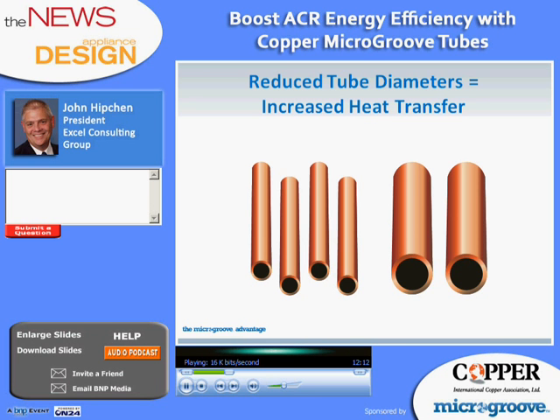Another benefit is that in a smaller diameter tube, we can hold the same pressure as a larger diameter tube, but we can do it with thinner tube walls. And we'll soon see in case studies how important this can be to the overall cost of a system. So, when we reduce tube diameters, we can actually reduce the weight of the materials being used and in turn reduce costs.